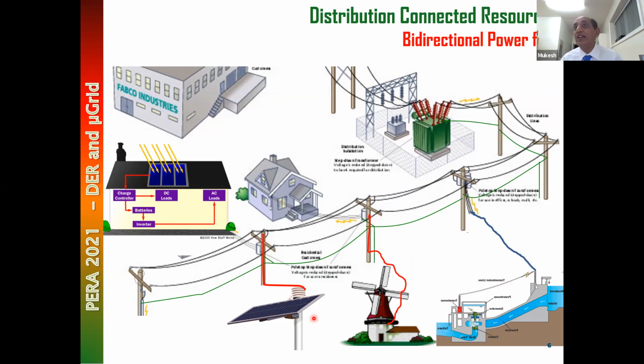It cannot be connected to a transmission system, to a high voltage system, because the cost of converting the voltage at which it generates the electricity and putting it at a high voltage is so expensive that the distributed generation connection at transmission level, or at least extra high voltage transmission level, using a traditional method is not viable, it's not practical. It is going to kill the distributed generation.